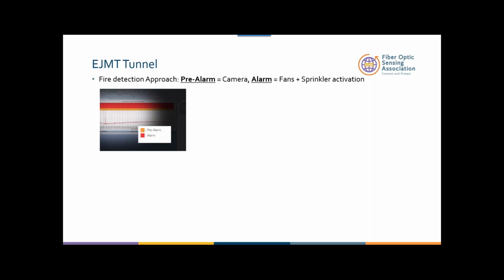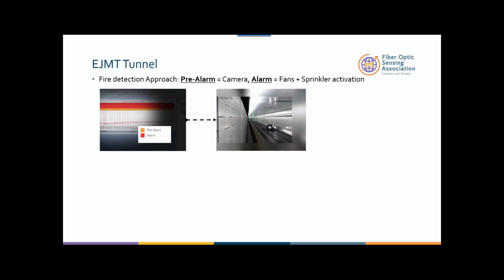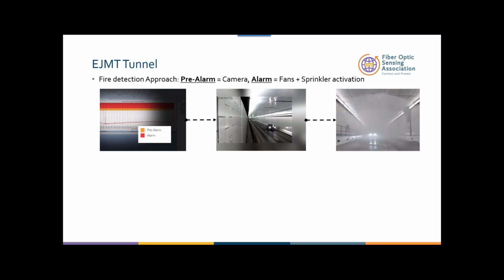You have a pre-alarm. The pre-alarm is if you reach a certain temperature, because you're monitoring the entire length of the cable from a thermal point of view. The pre-alarm is to activate the camera. The camera will zoom in and show the operator what's going on. And then the alarm will tell the fans that they need to be activated, and also the sprinkler system needs to be activated. Here's a picture of the pre-alarm showing, for instance, a vehicle coming in and the camera is on. And here's a picture depicting when the sprinkler system is going on.